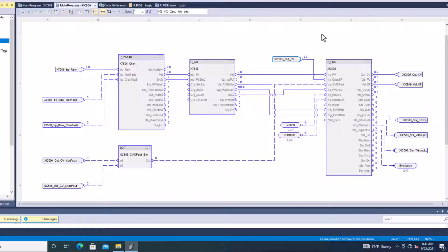And when it comes down to your PIDE loop, it's really specific to the reaction of your devices, you know, how long does it take the system to react, right? And all of your components in it, like say your valves or your pumps and your flows or pressures, how long does it take to actually react? That's going to be how you tune the actual drive or tune the PIDE loop.